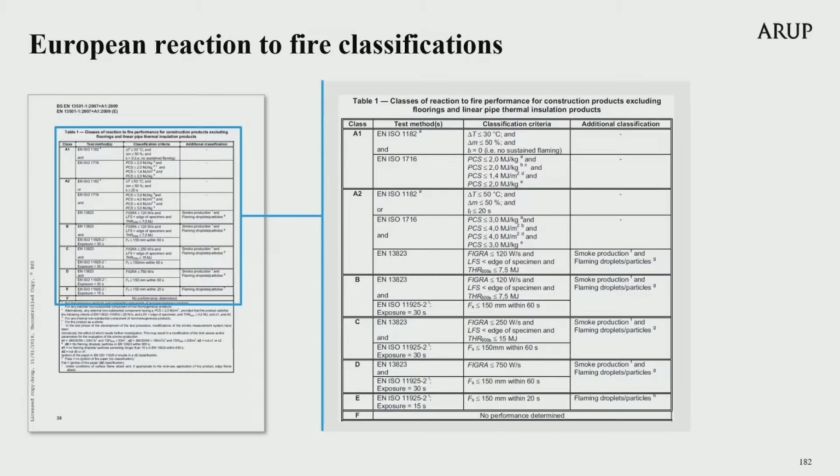First, in the classification standard, it provides at Table 1 all the different European classes. These are in letter form, unlike the national classes, which are typically numeric in form. For each class, this table states a classification can only be obtained by undertaking the tests or the extended application process required for that particular product.